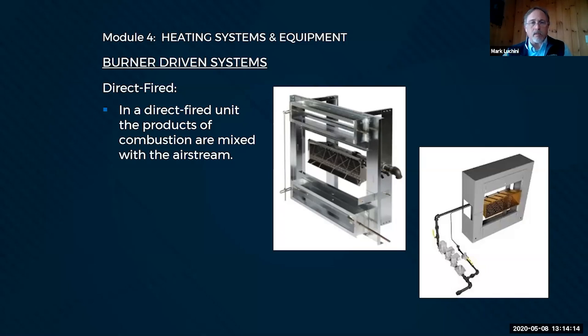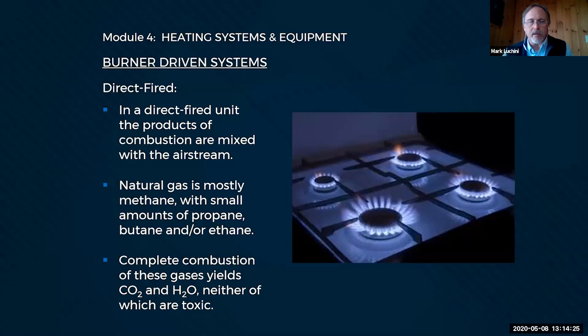Now you may be saying, is this kosher? We're putting products of combustion right into the air that people are breathing, and one thing to think about is we do it all the time, right? Anybody who's got a gas stove at home is doing the exact same thing. The thing to remember is natural gas is mostly methane. It has small amounts of some of the other alkanes in it, about 90% methane, 10% other stuff. But all of those fuels, if you burn them completely, you get CO2 and water. Neither of those obviously are toxic. I mean, the planet wouldn't exist without CO2 or water.